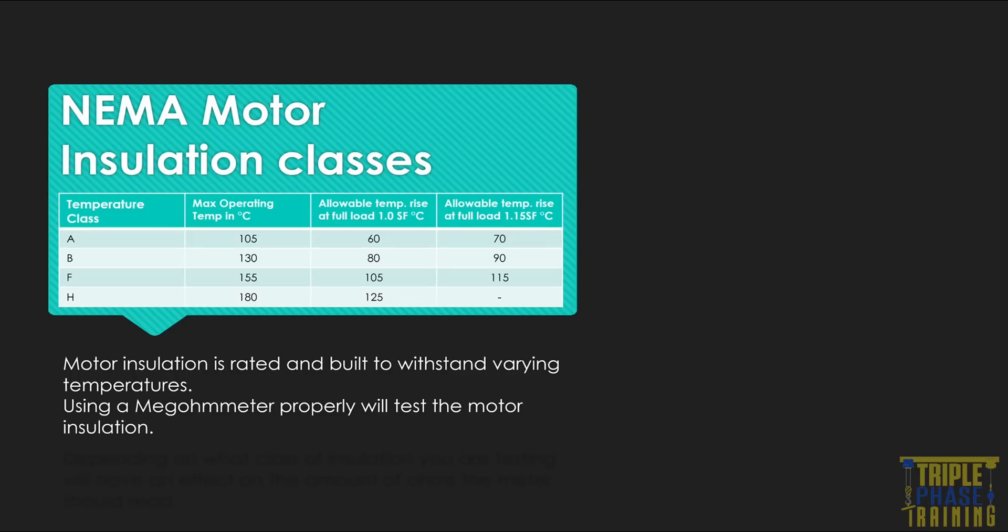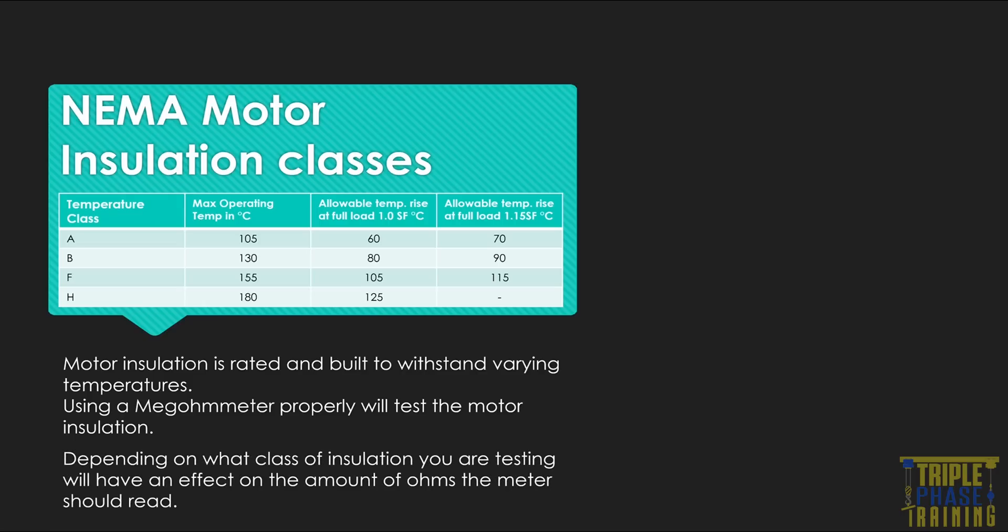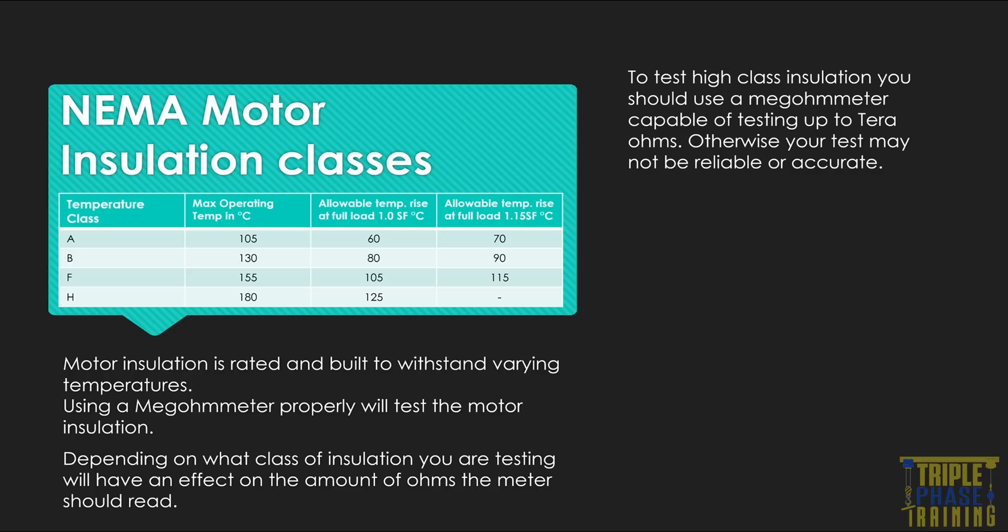Using a megohmmeter properly will test the motor insulation. Depending on what class of insulation you are testing will have an effect on the amount of ohms the meter should read. To test high class insulation, you should use a megohmmeter capable of testing into tera ohms. Otherwise, your test may not be reliable or accurate.